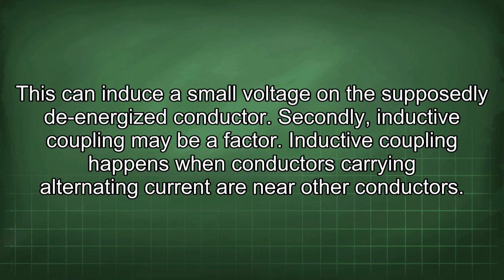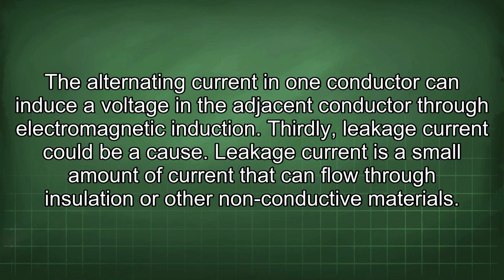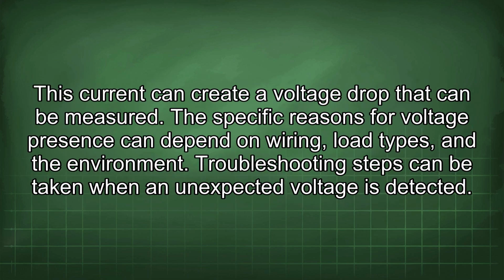Secondly, inductive coupling may be a factor. Inductive coupling happens when conductors carrying alternating current are near other conductors. The alternating current in one conductor can induce a voltage in the adjacent conductor through electromagnetic induction. Thirdly, leakage current could be a cause. Leakage current is a small amount of current that can flow through insulation or other non-conductive materials. This current can create a voltage drop that can be measured. The specific reasons for voltage presence can depend on wiring, load types, and the environment.